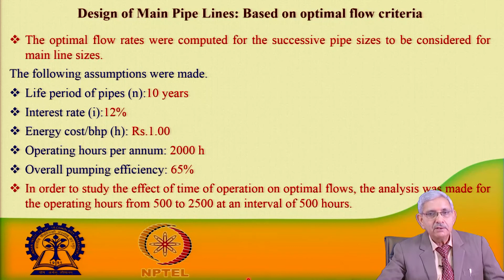So, here we can see these are the operating hours, and when we are considering these, the optimal flows estimated are given in the table, where this indicates the flow rate at which the pipe diameters can be changed from lower to higher for the consecutive pipe sizes of 63 millimeter to 75 millimeter and 75 to 90 millimeter. So, this way we are getting the values, and these values are optimal, at which the optimal flows are obtained.